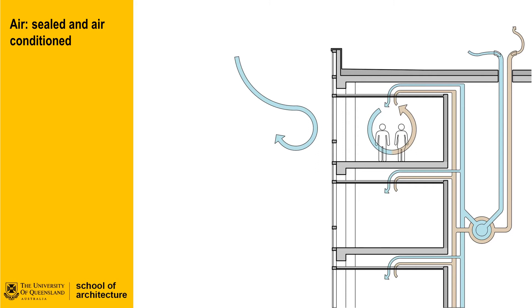Air conditioning of internal spaces is a necessary consequence of sealing our office workplaces. Though there is a degree of recirculation of air, mechanical systems work to exhaust stale air from work spaces and mix in fresh air from outside. If we used a full fresh air system which required conditioning, the energy use of the mechanical system would be extreme. A conditioning process that regulates the mix of recycled and fresh air is usually deployed to maximise mechanical efficiency.